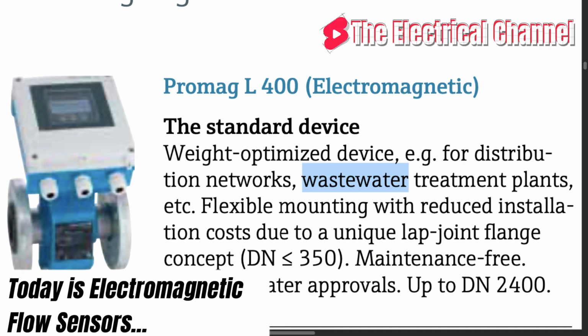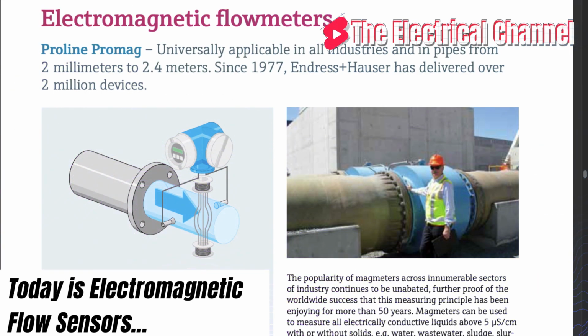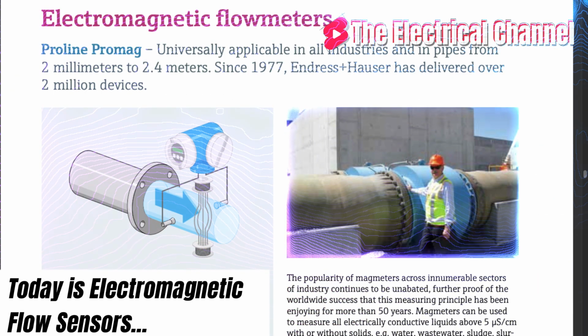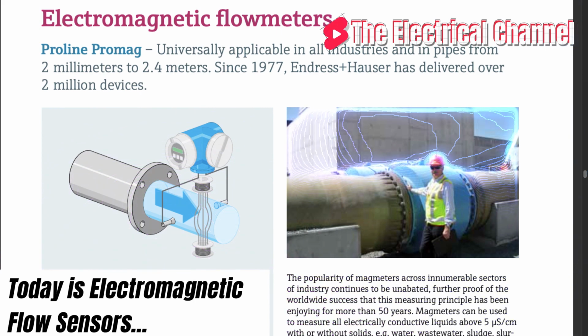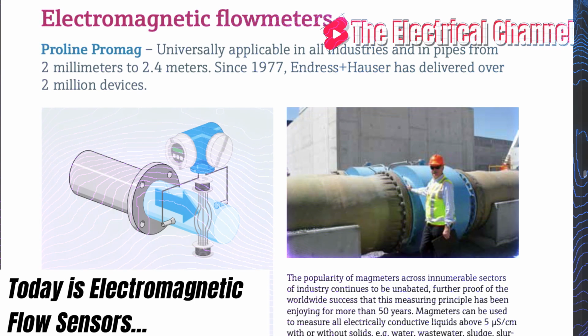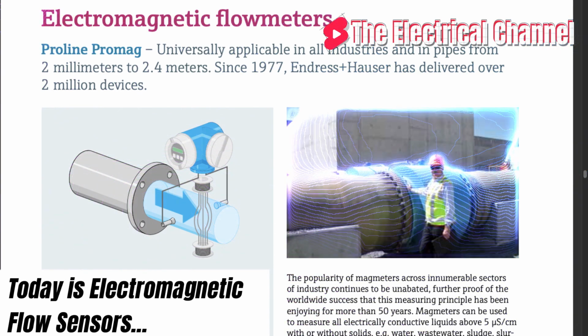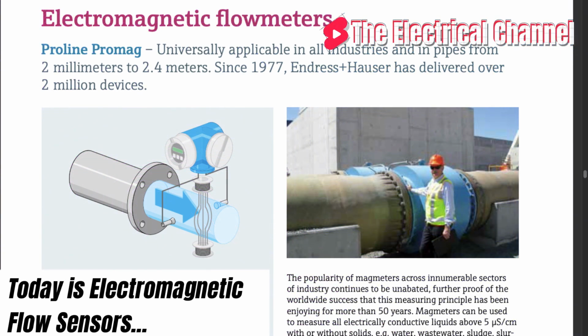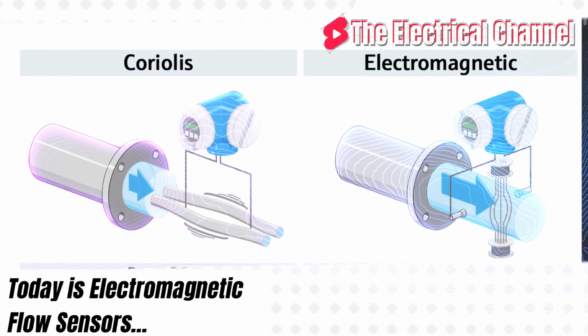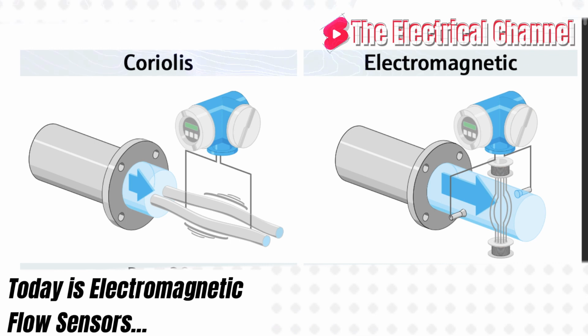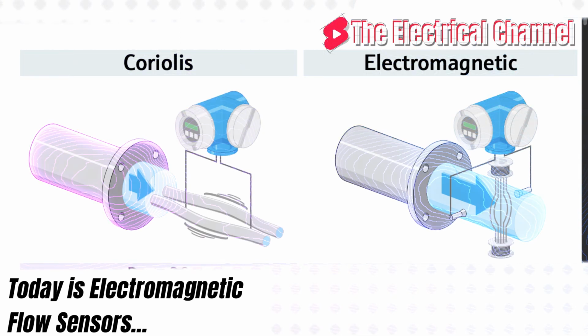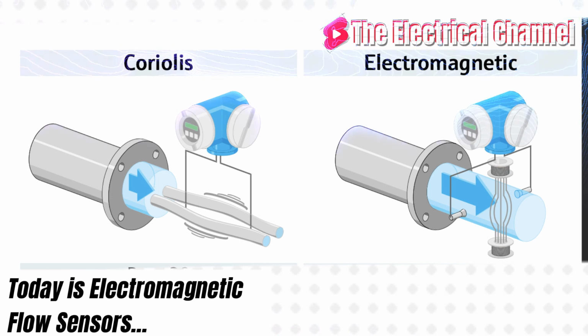The supply voltage, types of output signals and communications interface can be selected according to the customer requirements. The basic configuration flow meter includes two insulated passive binary outputs, each with an optocoupler including a transistor output. Insulated RS-485 communications, dry relay, 4 through 20 milliamp output, and the USB communication interface.